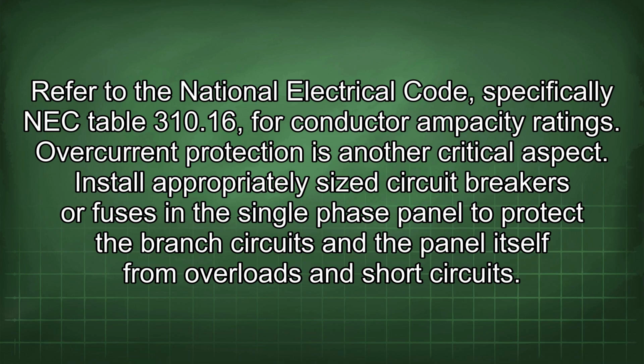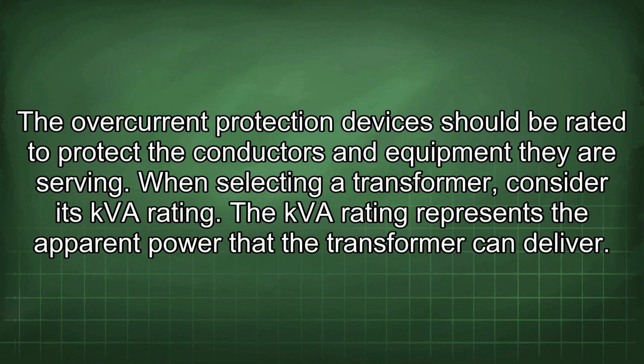Overcurrent protection is another critical aspect. Install appropriately sized circuit breakers or fuses in the single-phase panel to protect the branch circuits and the panel itself from overloads and short circuits. The overcurrent protection devices should be rated to protect the conductors and equipment they are serving.